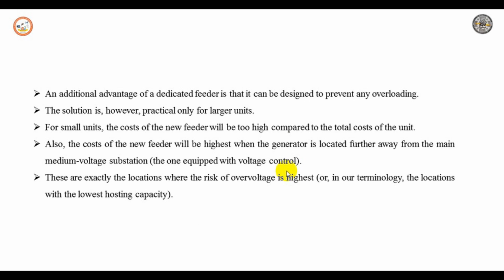An additional advantage of a dedicated feeder is that it can be designed to prevent any overloading. The solution is however practical only for larger units. For a smaller unit, the cost of a new feeder will be too high compared to the total cost of the unit. Also, the cost of a new feeder will be highest when the generator is located further away from the main medium voltage substation. So these are exactly the locations where the risk of over voltage is highest.